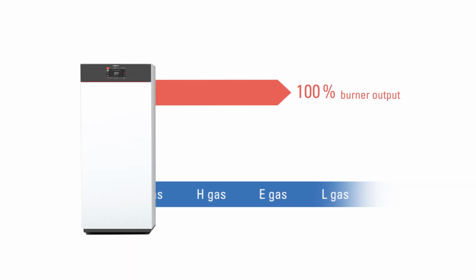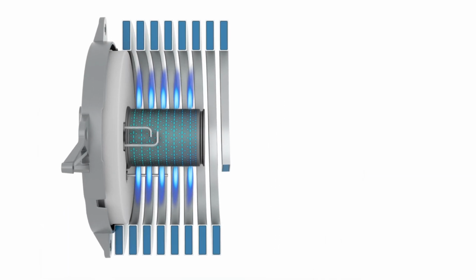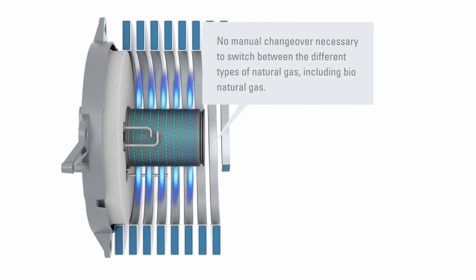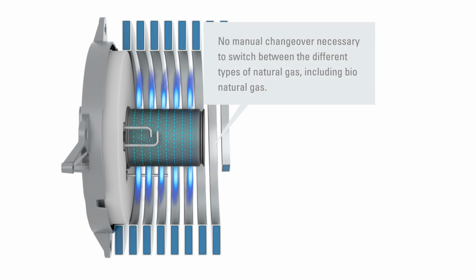You can freely switch between natural gas L or natural gas H. The new combustion controller adjusts the condensing boiler automatically without you having to lift a finger. Should the supplier change the gas type or the gas quality fluctuate, the Viessmann gas condensing boiler has already made the necessary changes behind the scenes. This makes manual adjustments and calibration during commissioning or a gas changeover superfluous.